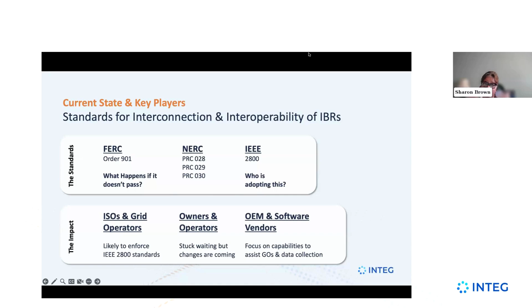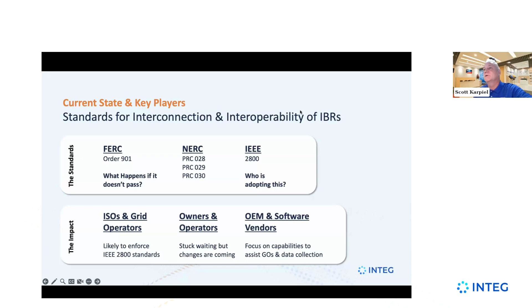So in addition to NERC, you have the industry standard. It's a good point, Sharon, because it makes things very difficult for OEMs and owners and operators when different locations and different ISOs have different requirements, trying to keep up with what each individual entity is doing within their own territory. So you really have to pay attention to those LGIAs, those interconnection agreements, as to what your plant operational needs and requirements are, especially when it comes to these events we're trying to prevent.